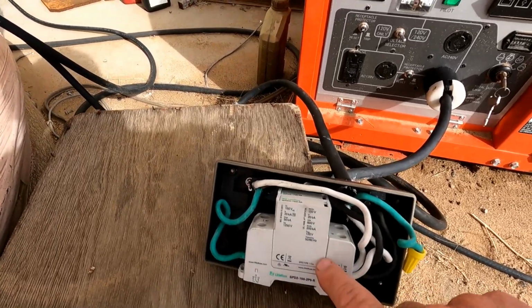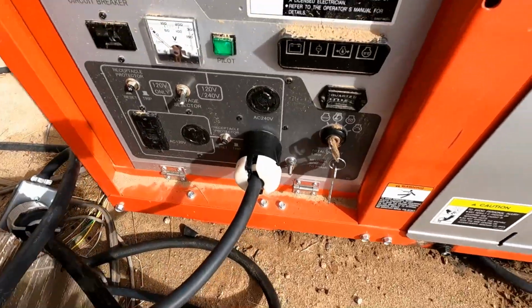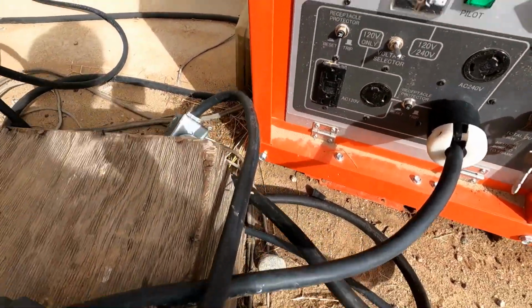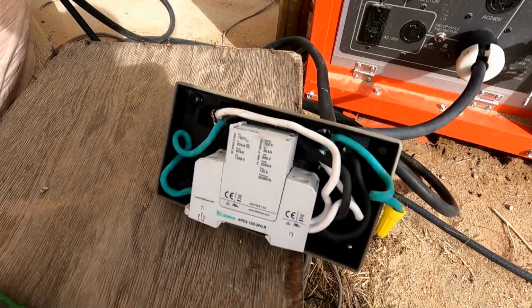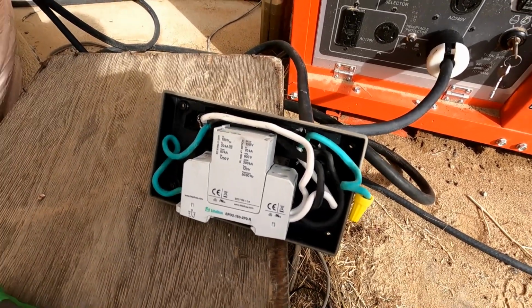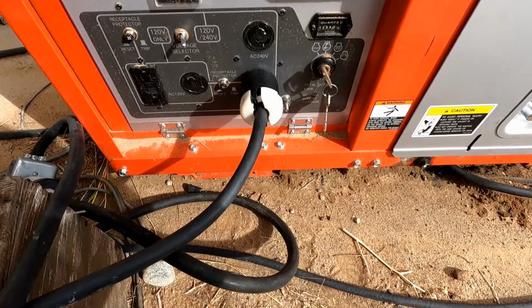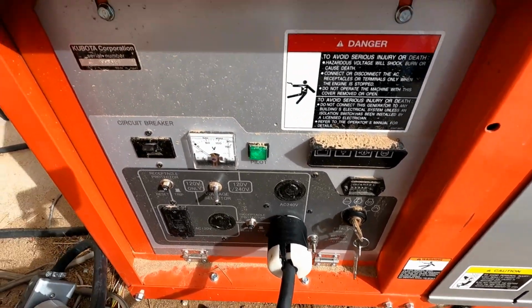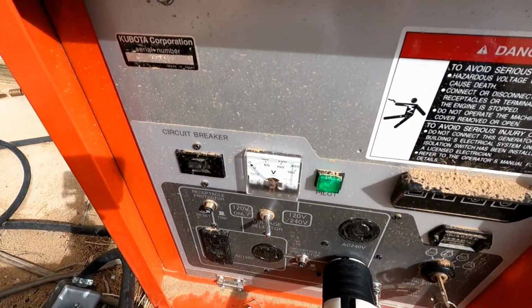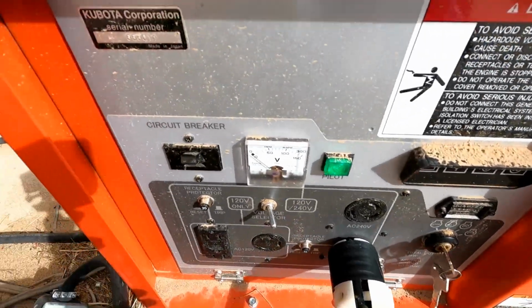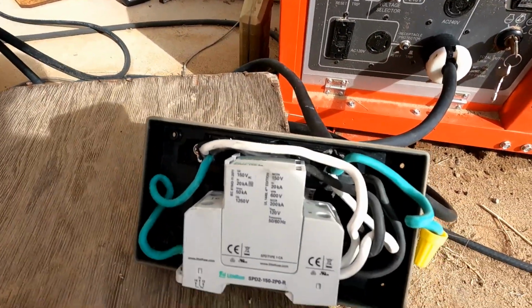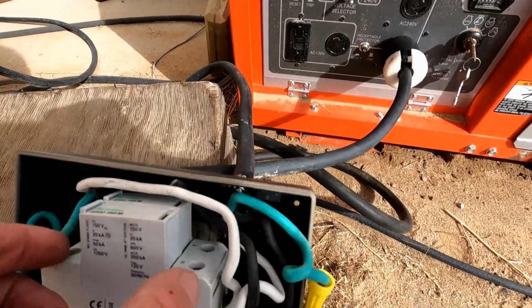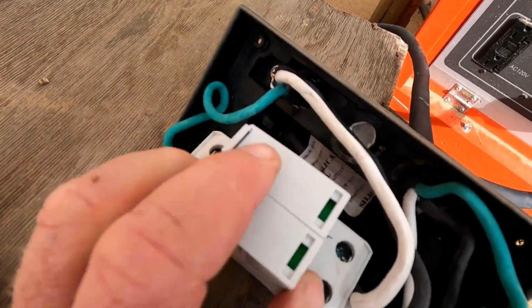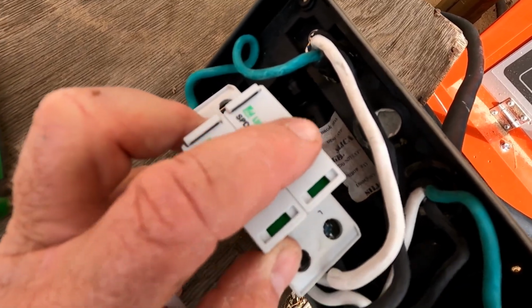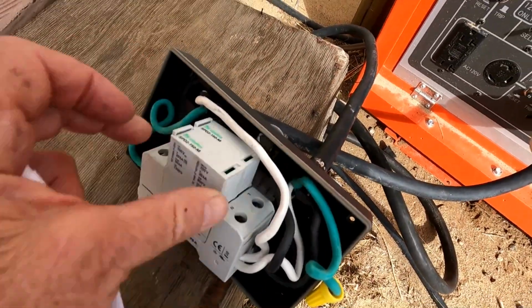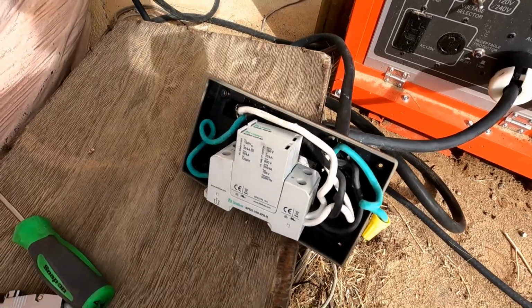This surge protector also needs to be added at the generator output line before it goes into the long line underground. So that way you're absorbing the energy before it gets into the generator. And you technical types, resist the temptation to put it in the generator ahead of the breaker. You want the generator breaker to function ahead of these in case the surge protector should short out. Note there's also a life indicator on these surge protectors. These two little green windows will turn red in the event that the life of the protector has ended.